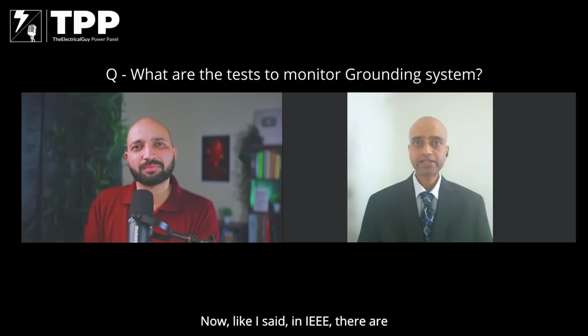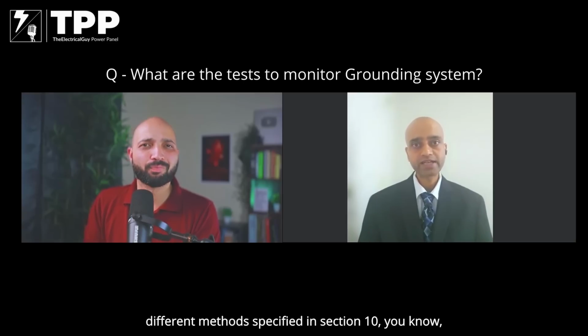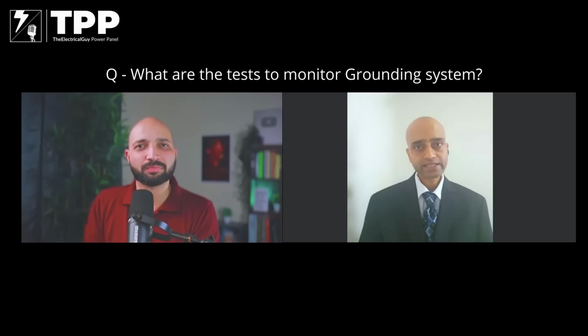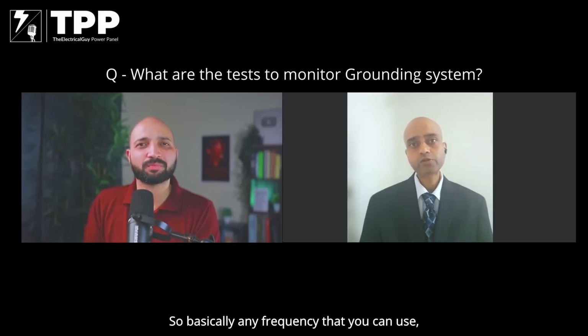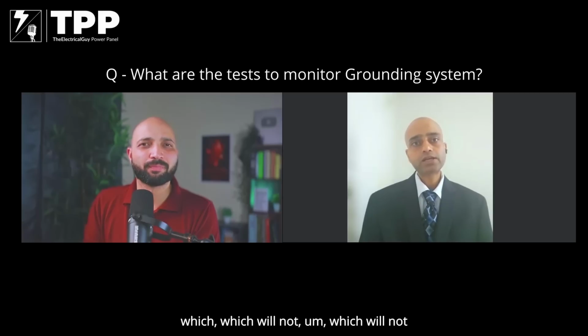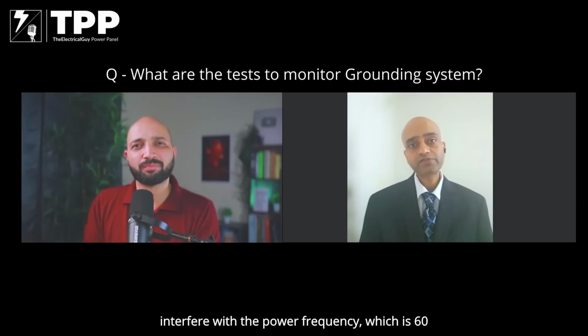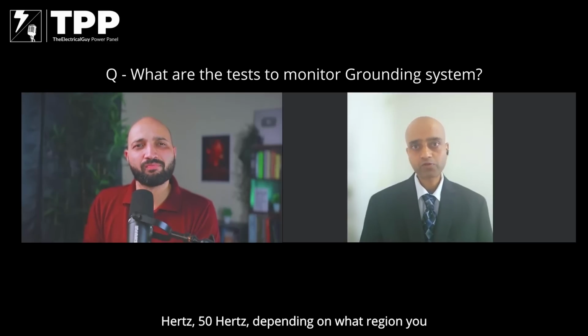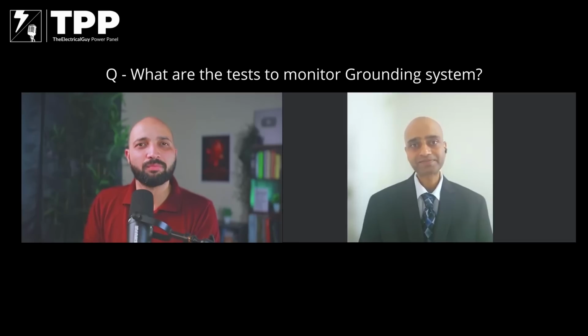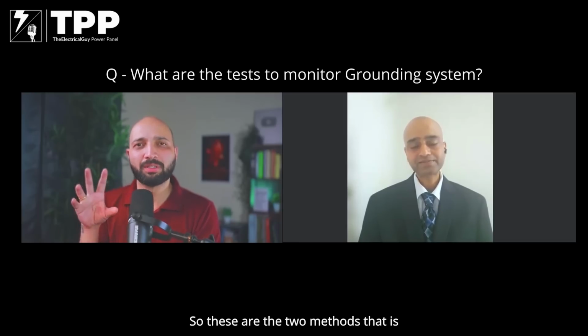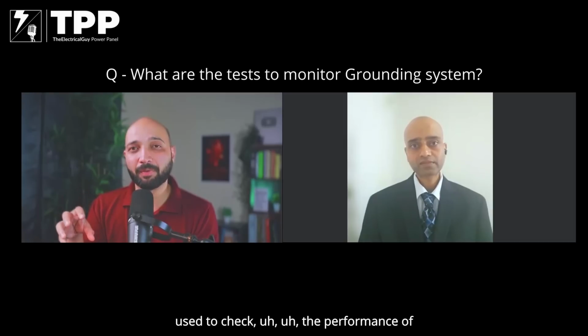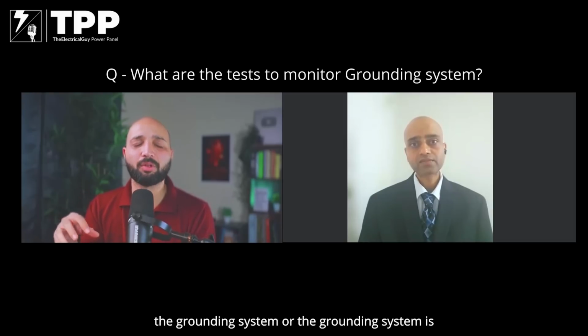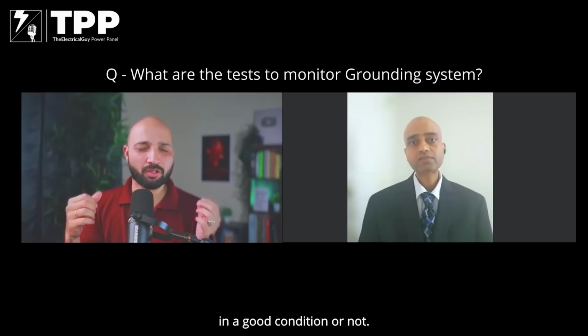Now, in IEEE, there are different methods specified in section 10. That could be a DC test, or high frequency - basically any frequency that will not interfere with the power frequency, which is 60 hertz or 50 hertz depending on what region you are in the world. So these are the two methods used to check the performance of the grounding system, or whether the grounding system is in good condition or not.